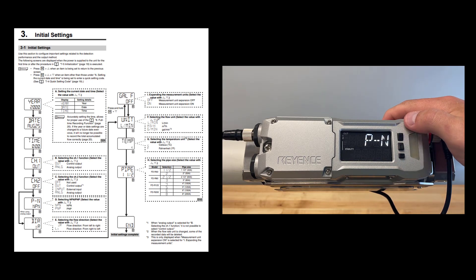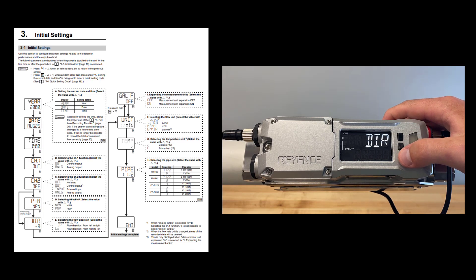Configure the signal that you need to come from these discrete outputs as being a PNP 24 volt output, or an NPN 0 volt output. Set the direction at which the flow of the liquid is going as either being from left to right, or from right to left.